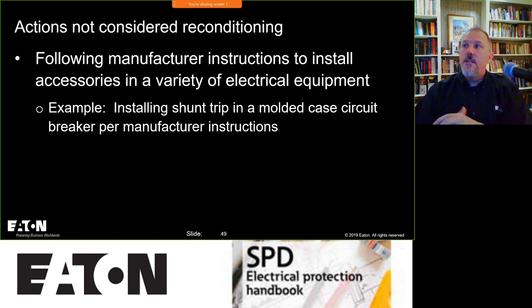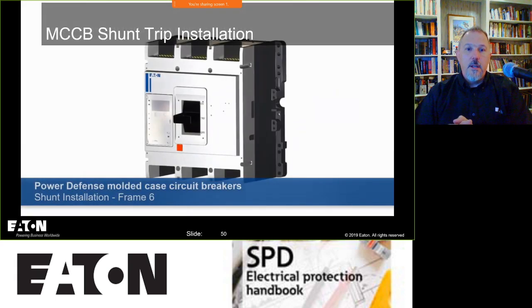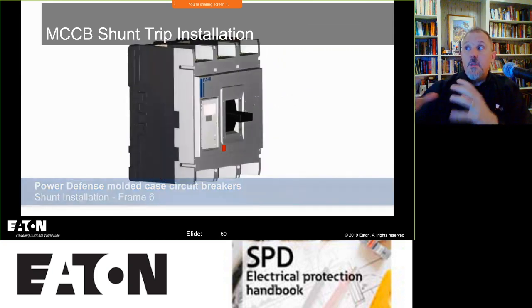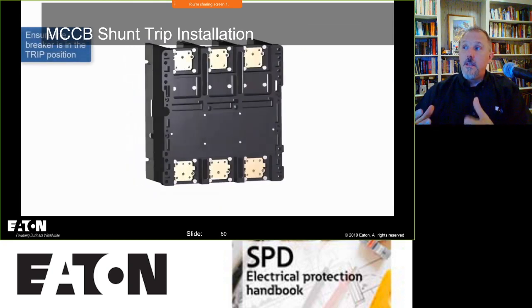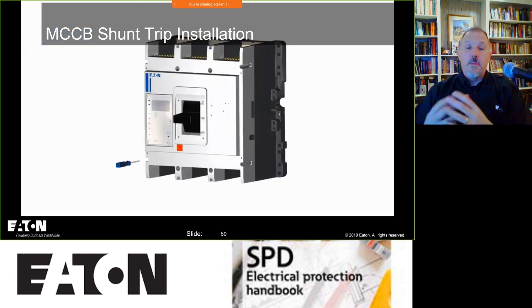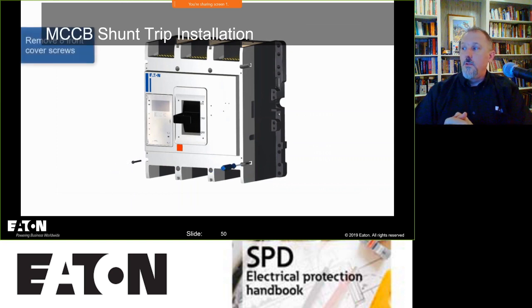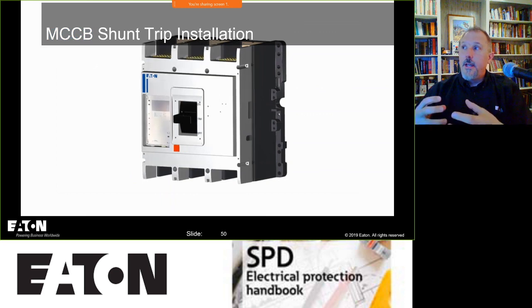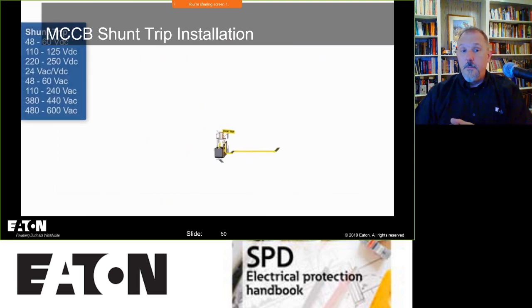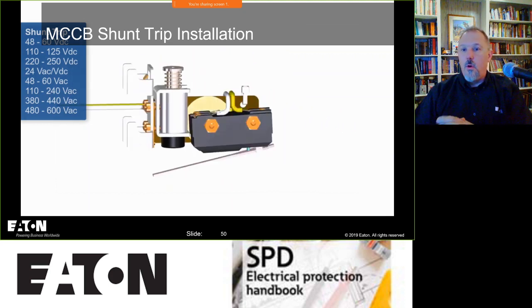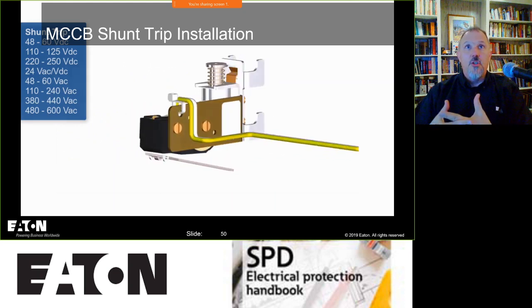Now, actions, again, if you follow manufacturer's instructions to install accessories in a variety of equipment, installing a shunt trip, for example, in a molded case circuit breaker, is one of those examples where you'd say, well, this process looks pretty intrusive, Tom. You're taking the front of this breaker off and exposing a lot of the parts inside. You've got to remove all these screws. Now, the key thing is this product was designed to be opened this way. There are a lot of molded case circuit breakers, and you'll see the little stickers on the side. The screws weren't designed to be taken out and put back in again. Some of those are self-tapping screws or rivets, and you can't take them out and put them back in, and they're not going to hold like they would from an original manufacturer's perspective.